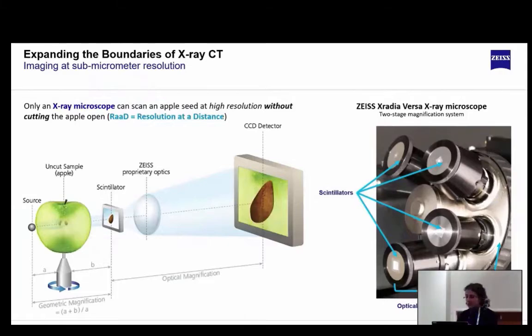And just to illustrate one more time with a very hypothetical example, think about an apple. I don't want to compromise any customer part here, but this is an easy example. Just think that you want to scan the seed of the apple without opening the apple. If you use the X-ray microscope, then you can easily zoom in on a region of interest, because the optical magnification is going to allow you to keep the resolution. And you can see that we have several scintillators on top of the lenses that are just behind. Those are the optical magnifications behind that. And after that, the visual is converted by a CCD detector into a signal that goes to a screen.